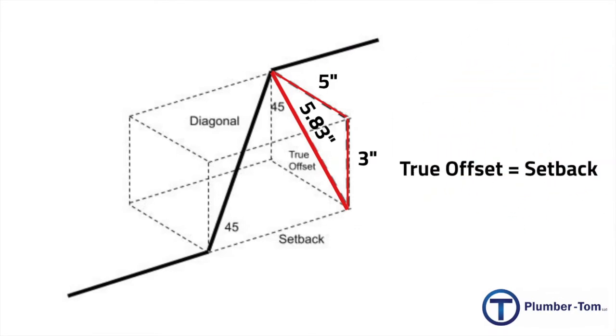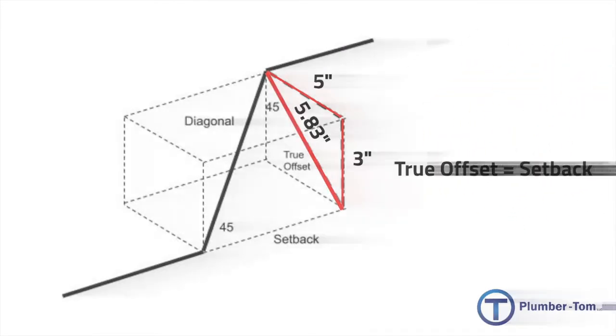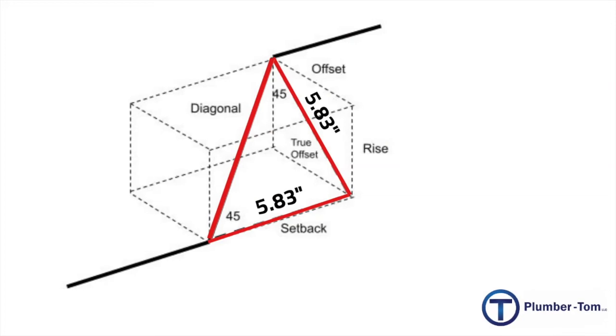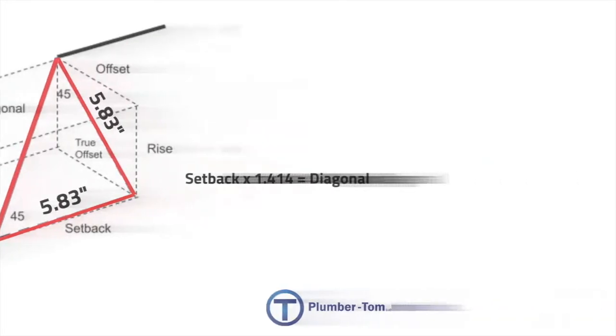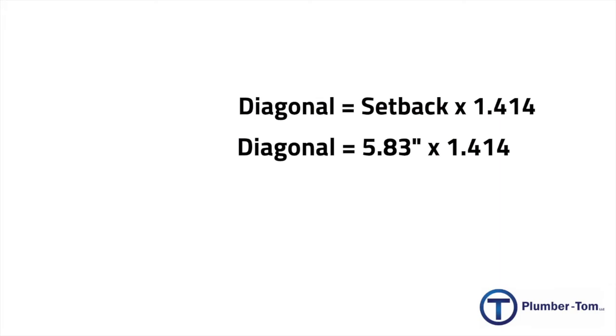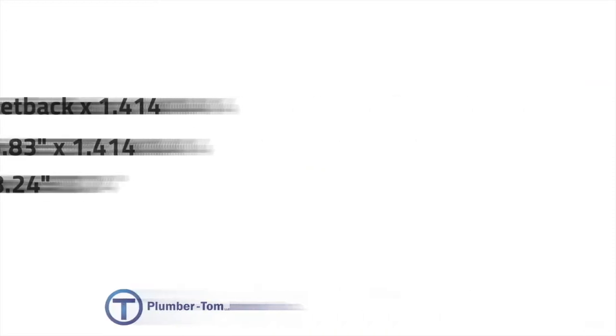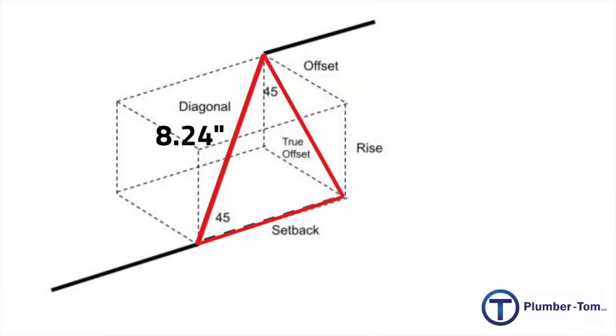So now we know that our triangle with an offset of 5 and a rise of 3 has a diagonal of 5.83. This 5.83 is the true offset, which is equal to the setback. Now we go back to working with our triangle that has two 45-degree angles and two sides that are the same. We've calculated the true offset and the setback at 5.83. To find the diagonal — which is where our pipe will run — we multiply the setback by 1.414. So that would be 5.83 × 1.414, giving us a diagonal of 8.24. We have calculated our rolling offset.